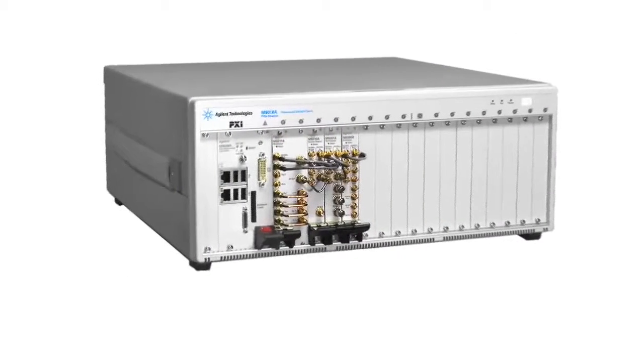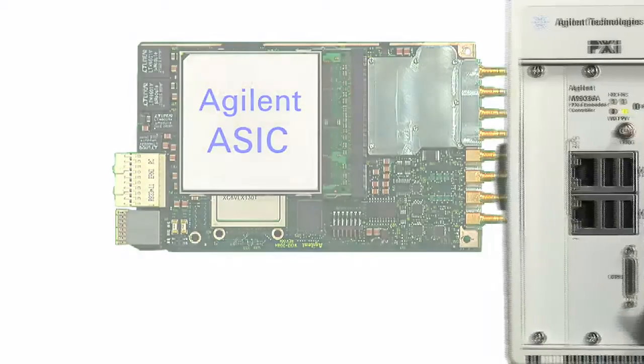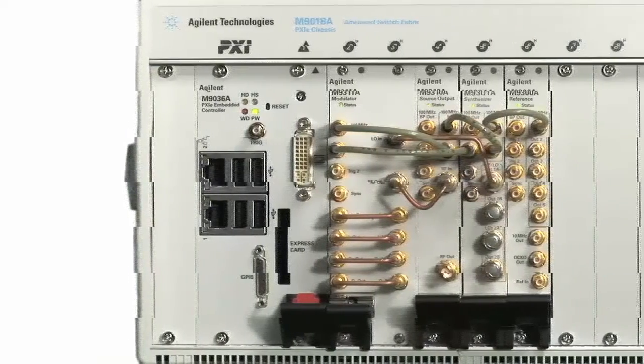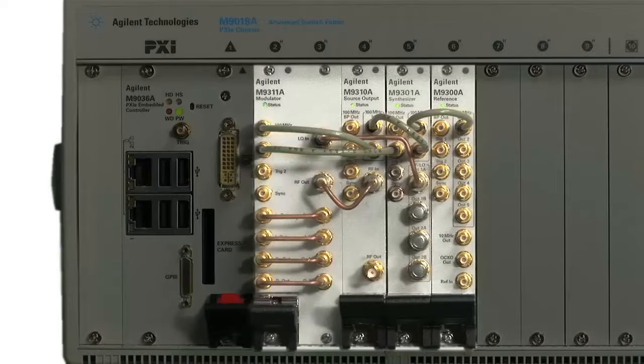We've achieved this breakthrough performance by using Agilent's unique components and innovative designs such as our proprietary baseband ASIC. The Agilent M9381A VSG consists of four PXIE modules. Three of these modules can also be configured as an RF-CW source, the M9380A.